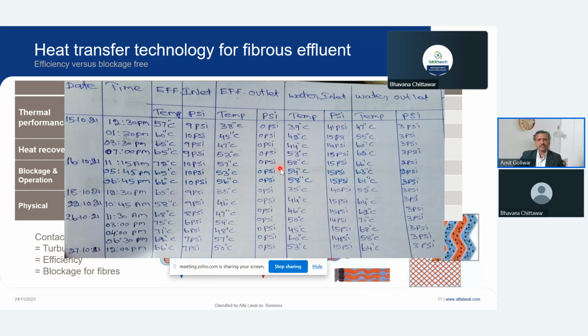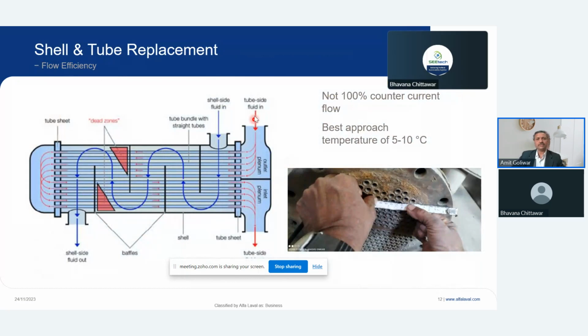Having said that about the shell and tube disadvantage, to know the disadvantage, you need to see how shell and tube operate. Shell and tube normally operate with multiple passes. So this is a typical drawing where two passes are given. So in the first pass, this is the shell side and this is the tube side. If you look at the shell side, this is co-current, and on the other side, this is counter current. However, if you look at a plate heat exchanger, it is your choice. You can have counter flow also. And if you go for a counter flow, you can achieve the approach as low as 1 degree. But in shell and tube, it is not possible. And our observation is, if you replace shell and tube with a plate heat exchanger, again, provided the duty conditions and the fluid allow, you easily get a saving, and the payback is less than a year.